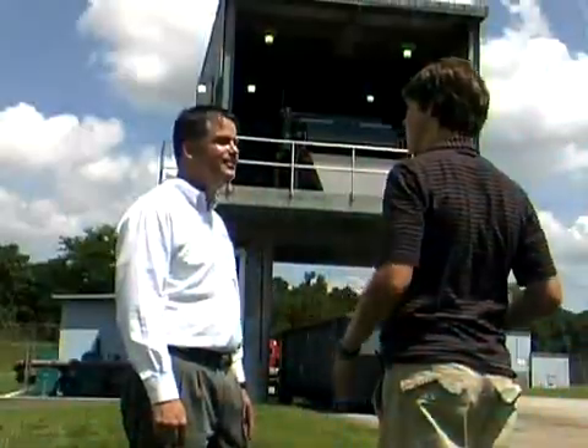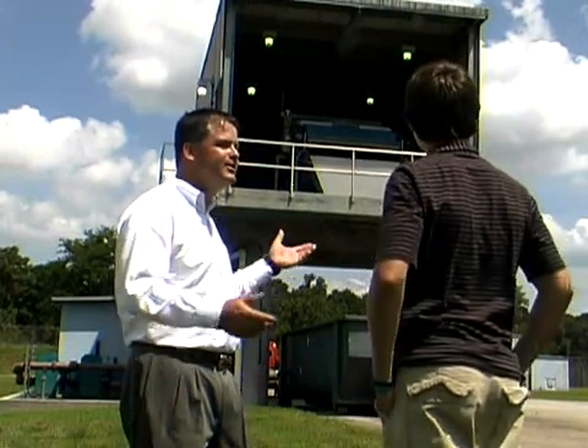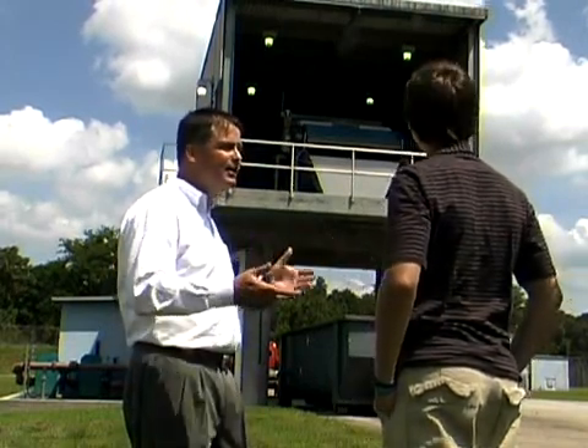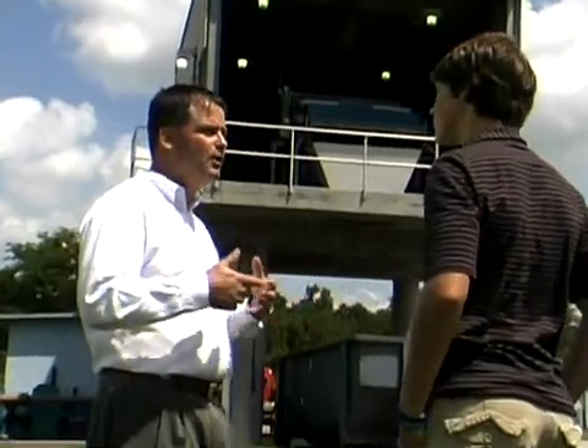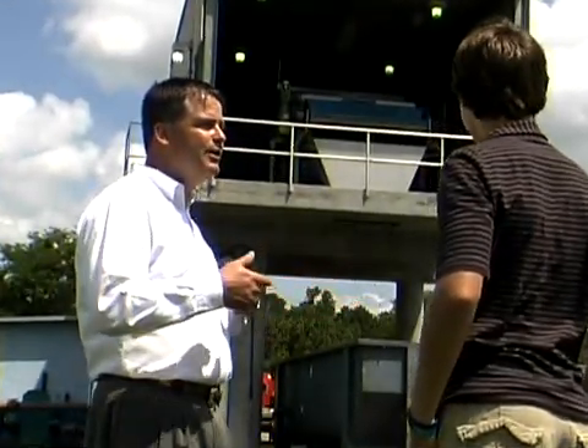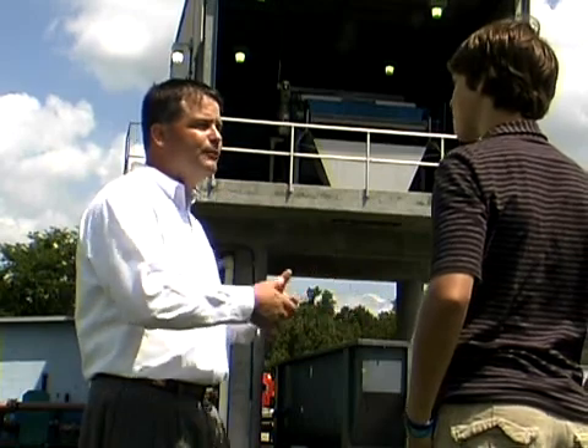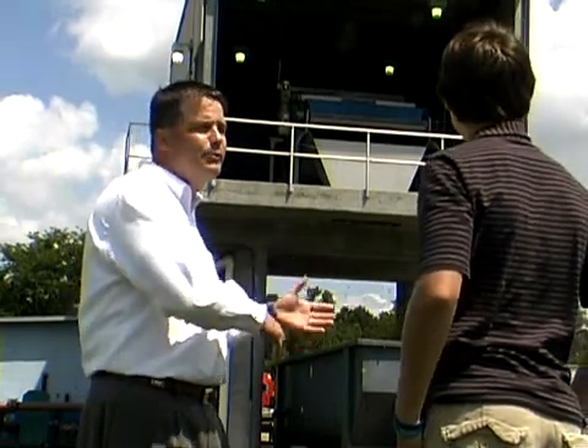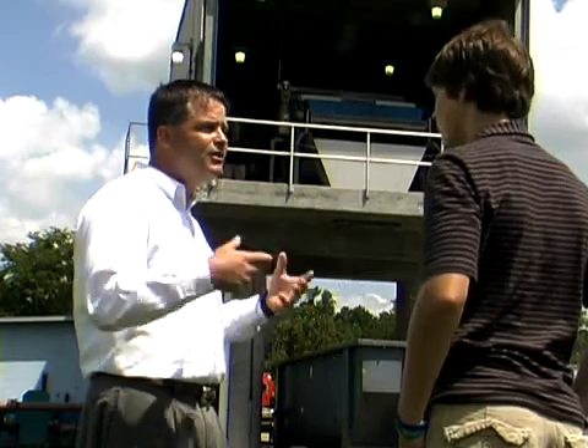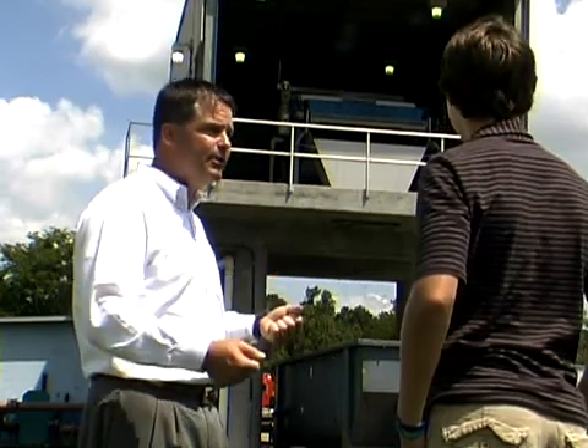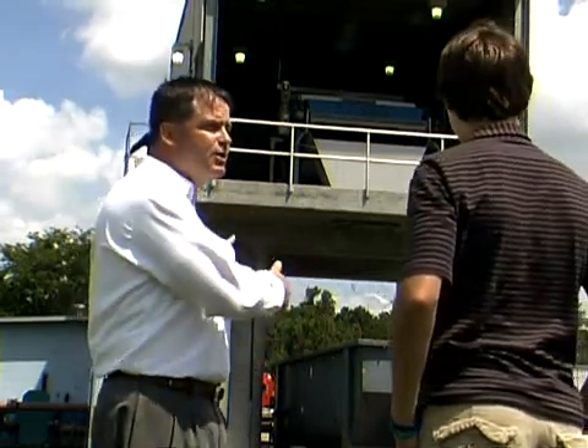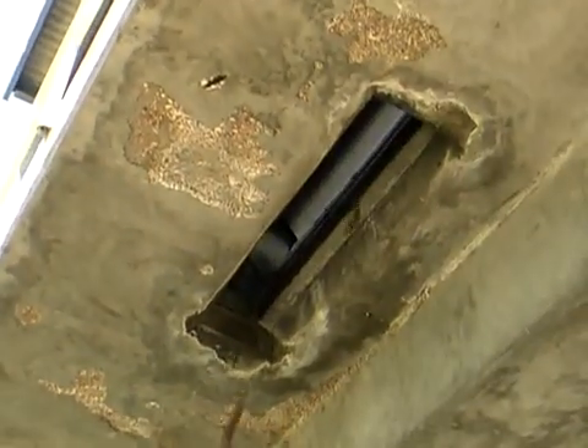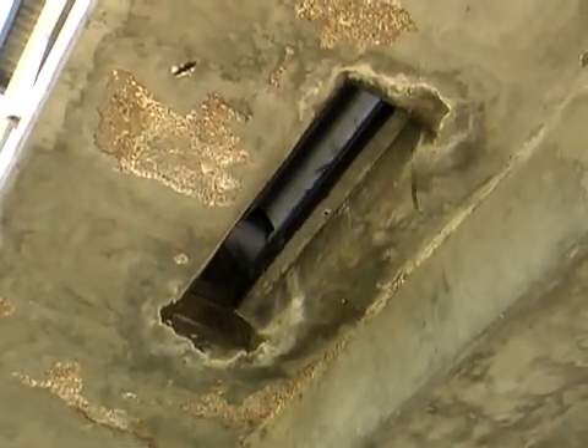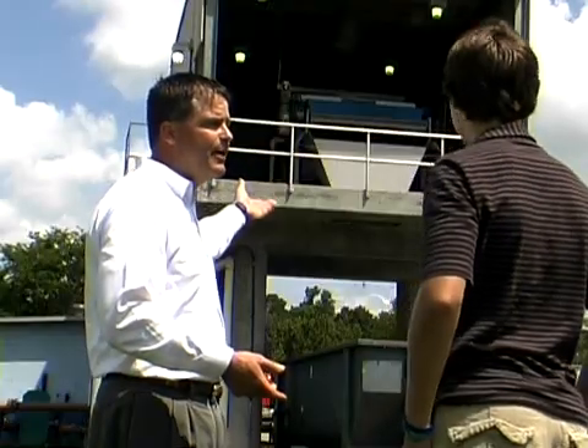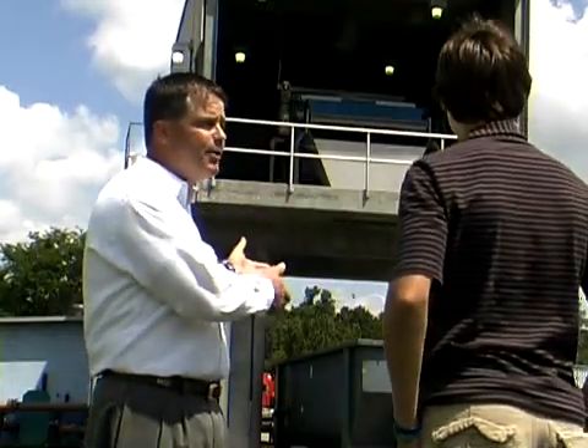That's correct. This must be the sludge press you were telling me about. That's right, this is the sludge press. I wanted to stop by so you could see this before we were done. This is really the final process for what we've removed from the wastewater. I told you that we put the wastewater into the treatment plant and convert it into bacteria. Take the extra bacteria we grow every day, put it in the digester. In the digester, we concentrate it, reduce the total amount of bacteria in there. Eventually it makes its way over to the sludge press. The purpose of the sludge press is to remove as much water as possible. We'll probably have a total solids concentration by weight of 15 to 20% coming off the belt press.